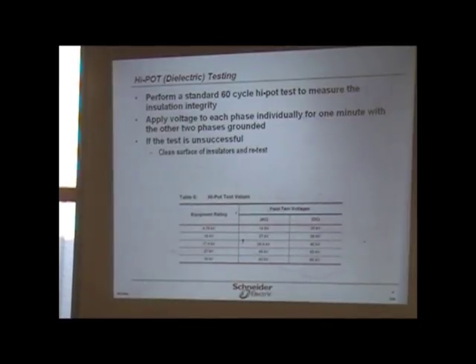Remember, like I said, the fuses, if you replace one, replace them all. Make sure that the striker pin, here's that high pot value we were just talking about. See? So replace all fuses. Yes. And hold the other two as your spares. See how it says apply the voltage? I told you yesterday, for 1 minute with the other two phases grounded.